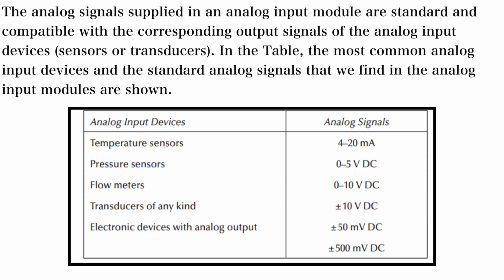First is the temperature sensor, having an analog signal range of 4 to 20 milliampere. Next, the pressure sensors, having an analog signal range of 0 to 5 volt DC. Flow meters have an analog signal range of 0 to 10 volt DC. Next, transducers of any type generally have a plus minus 10 volt DC analog signal range. Next, electronic devices with analog output generally have an analog signal range of plus minus 50 millivolt DC, or plus minus 500 millivolt DC.